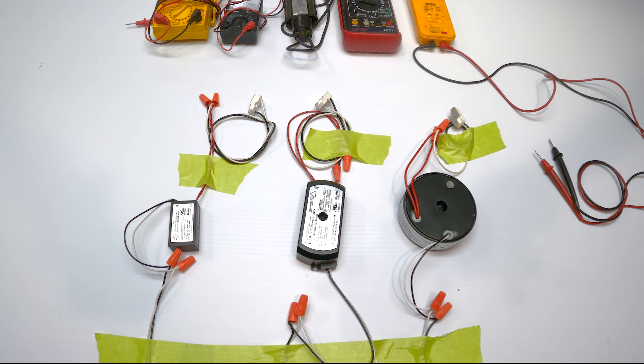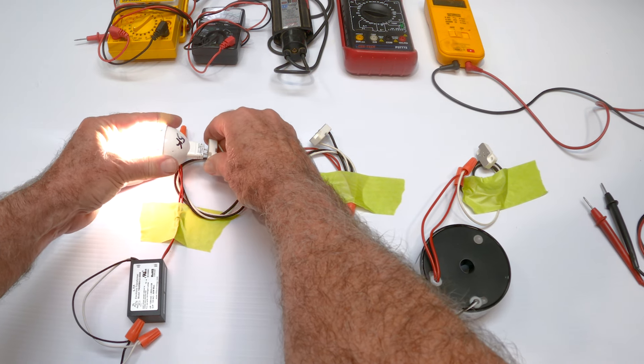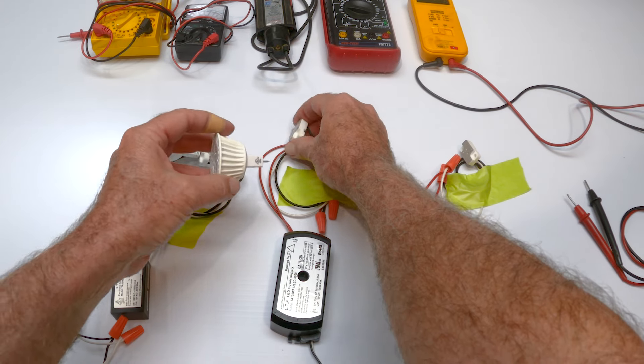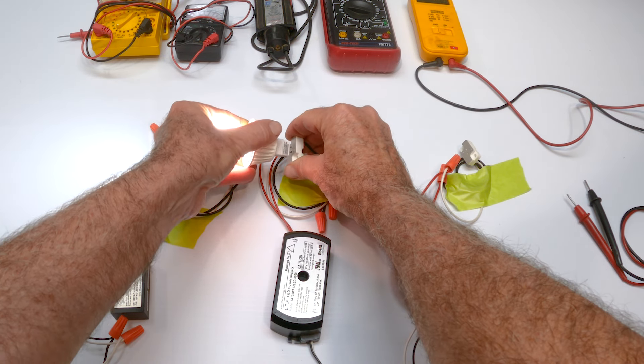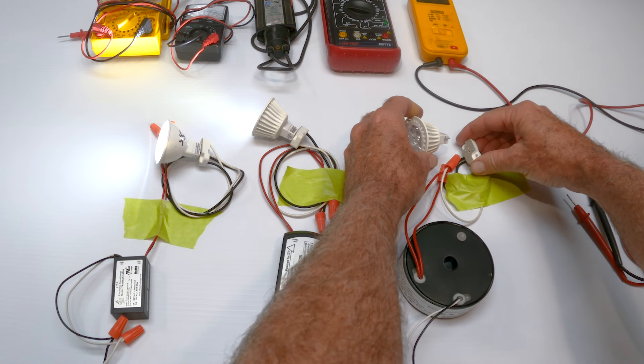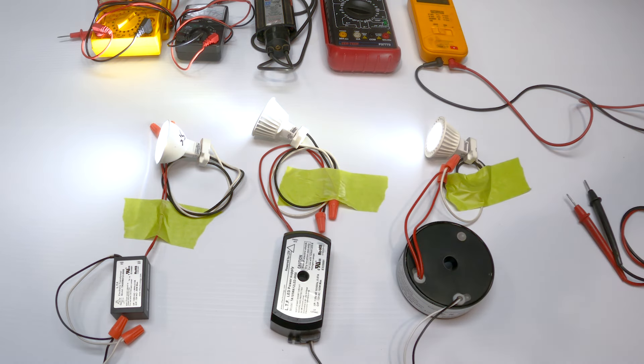So let's see if these three transformers that were returned to us are actually defective. So I'm going to just take a 12 volt light bulb, this is an LED bulb, and I'm going to put it in each socket. And as you can see, all the light bulbs light up. So we know that the problem isn't the transformer, but it really could be somewhere else in the circuit.